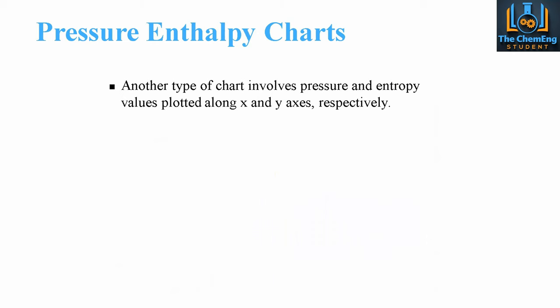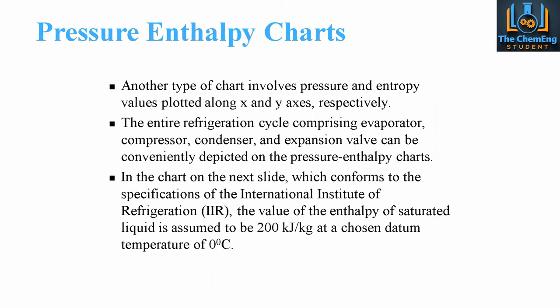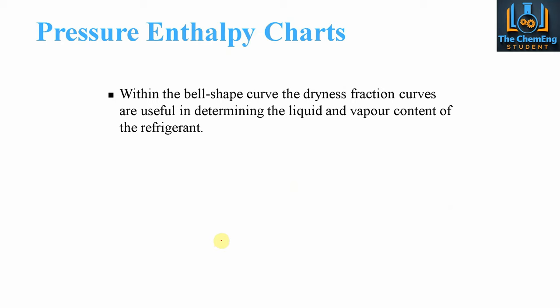Another chart type plots pressure and enthalpy on the x and y axes. The entire refrigeration cycle — comprising the evaporator, compressor, condenser, and expansion valve — is conveniently depicted on a pressure-enthalpy chart. Per the International Institute of Refrigeration (IIR) convention, the enthalpy of saturated liquid is assumed to be 200 kJ/kg at a chosen temperature of 0°C. Within the bell-shaped curve, the dryness fraction curves are useful in determining the liquid and vapor content of the refrigerant — a key parameter showing how much energy can be transported to vaporize saturated liquid into saturated vapor.